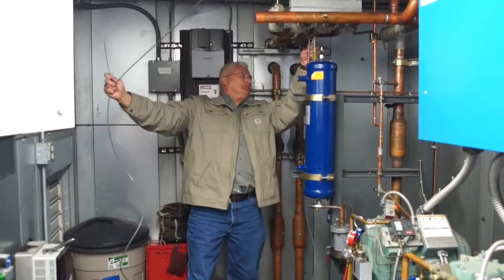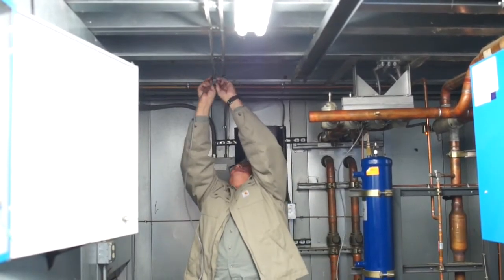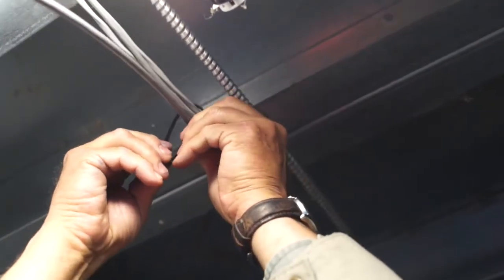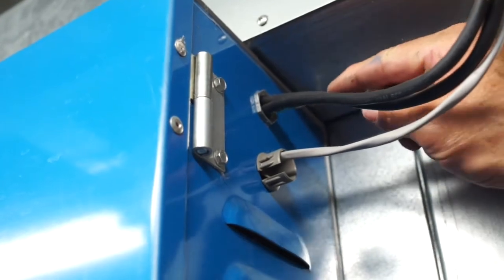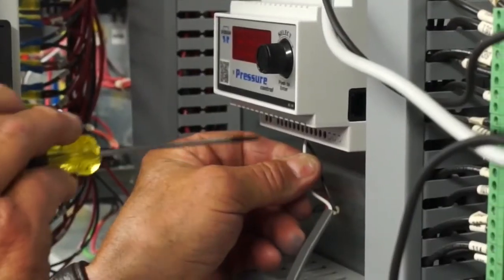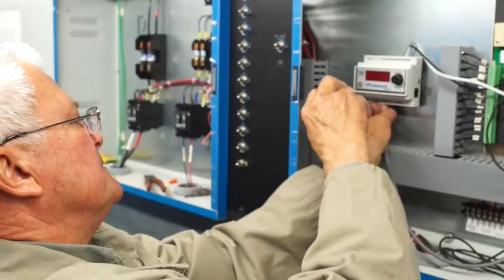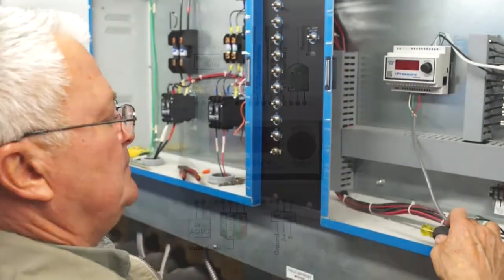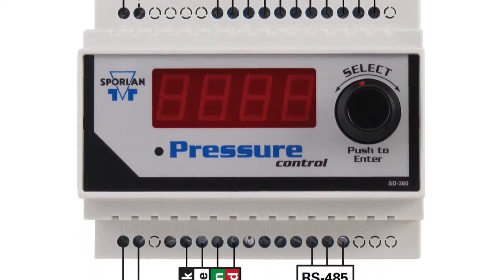You're now ready to wire the CDS valve. Route the conversion kit cable to the appropriate control panel. Prevent damage to the cable by using grommets or strain reliefs whenever the cable passes through the panel or any metallic bulkhead. Take care that the cable routes avoid hot pipes or sharp edges and make sure to properly support the cable throughout the route. Connect the four cable leads to the Sporlan pressure or temperature control, or to a suitable third-party control or interface board. Refer to the control manufacturer's recommendations for the correct wiring sequence.